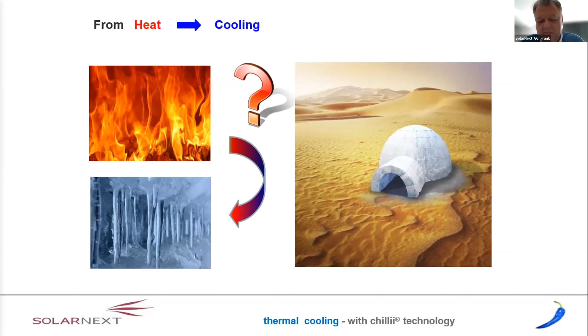The difference between absorption and compression chillers—compression is the mainly used technology. The main difference, as you see below, is that we use thermal heat. Our thermal COP is between 0.65 and 1.5, depending on the model and how many degrees of heat you can use.